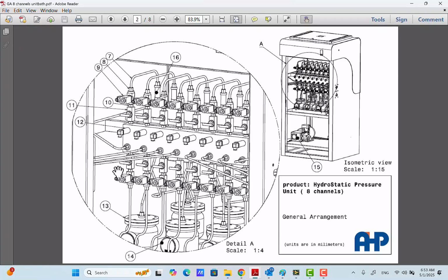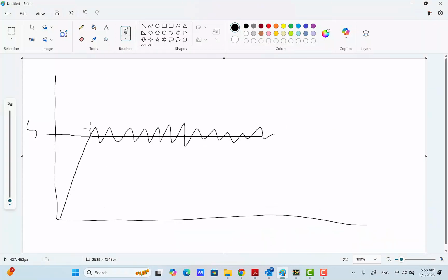Then this needle valve is important in how much water will be released for compensating overshoot of the pressure inside the sample. This needle valve will be almost closed. I mean, a very small, tiny amount of the downside needle valve will be opened. One degree is enough, for example, or less, so that it reduces the pressure very slowly in case of overshoot in the set pressure of the line.